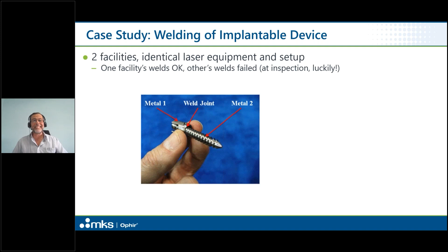They were producing this, maybe they still are, simultaneously at two separate plants. Strangely, the parts coming out of one plant were fine. The parts coming out of the other plant had a high degree of failure due to faulty welds, laser welding, okay? And luckily, the flaws were all found at inspection and not, God forbid, inside a patient. But they couldn't figure out what was going on because in both plants the setup was the same, the process was the same, the equipment, the lasers, everything was supposed to be two identical production lines, and yet one was producing good parts and the other one was producing scrap.